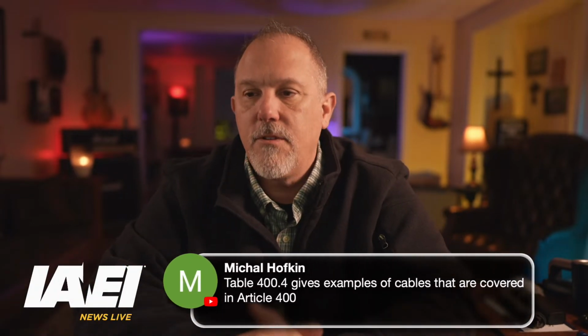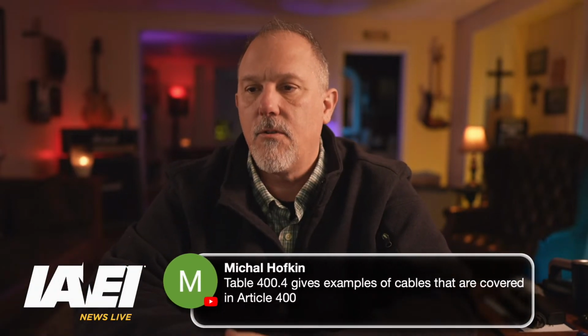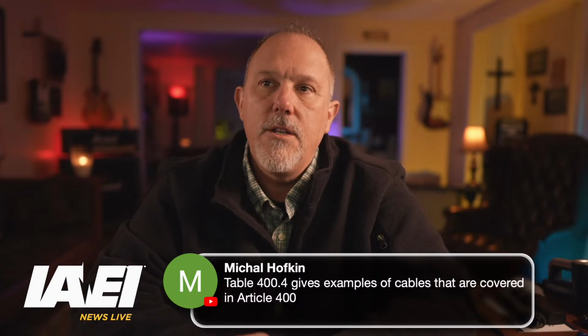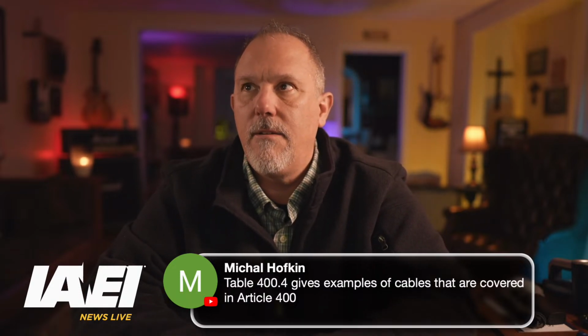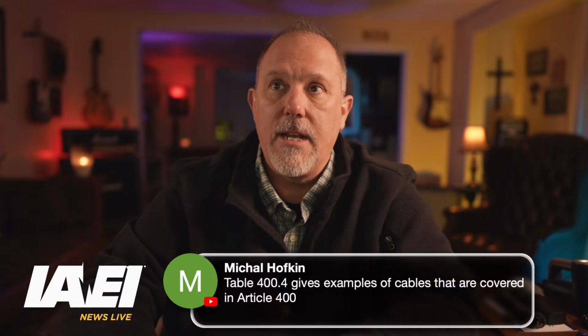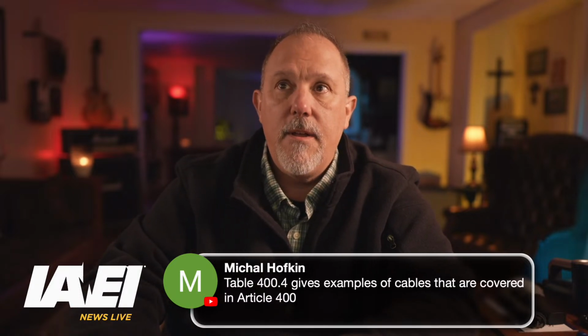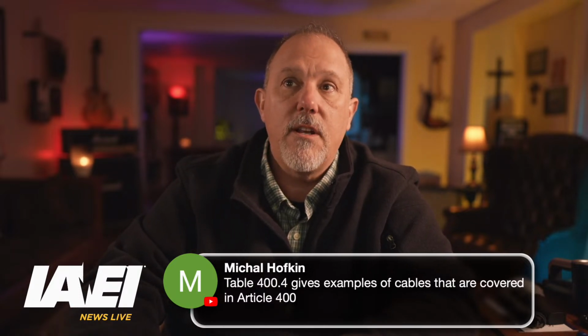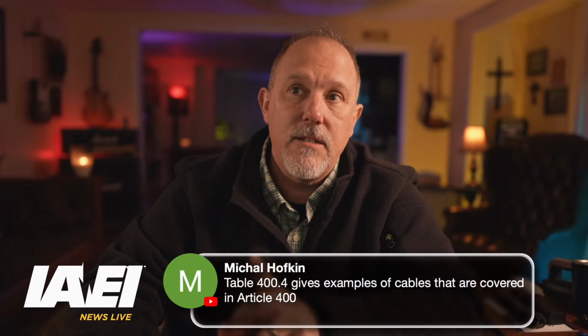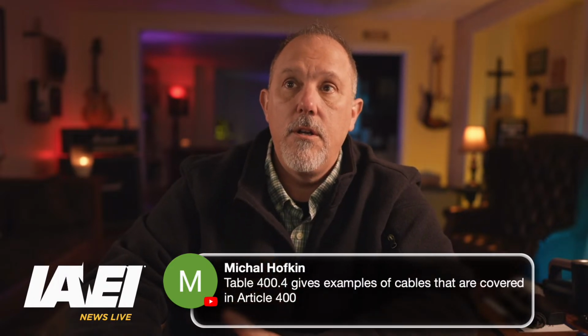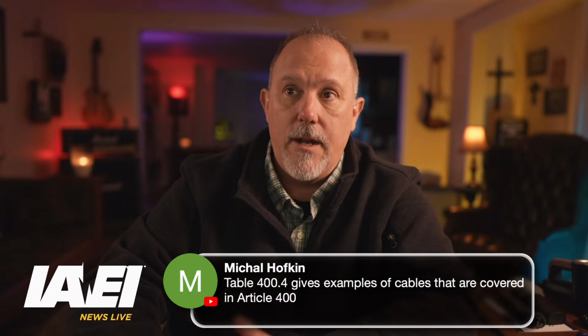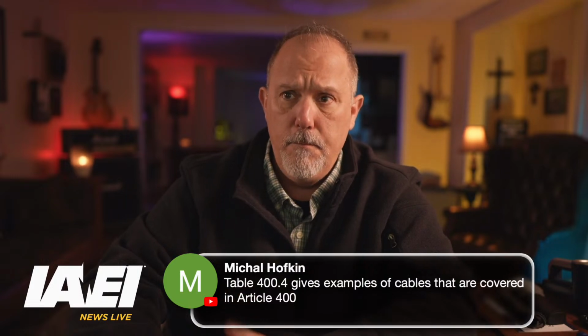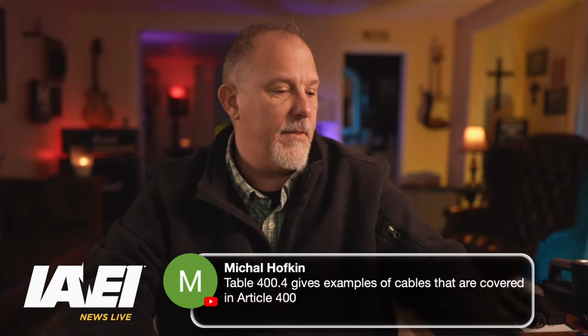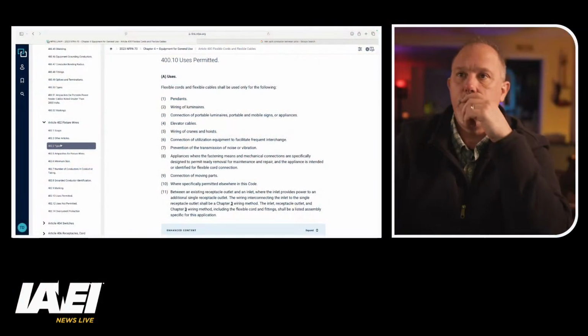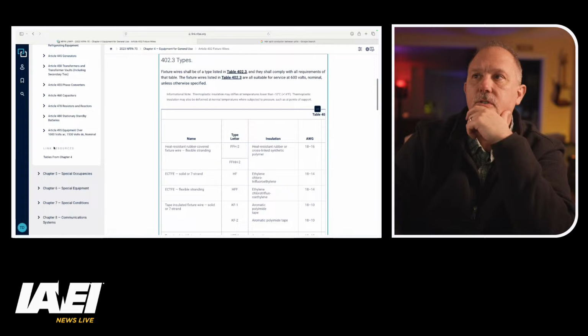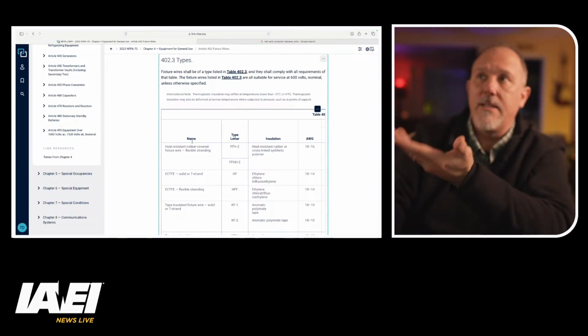Okay, table 400.4 gives examples of cables that are covered in Article 400.4. So it does, Michael, and that helps considerably. If you look at flexible, that's flexible. If you look at fixture wires, I would expect 402. If I go to fixture wires, I don't have a similar thing for fixture wires. 402.3, yes I do -- 402.3 is types.